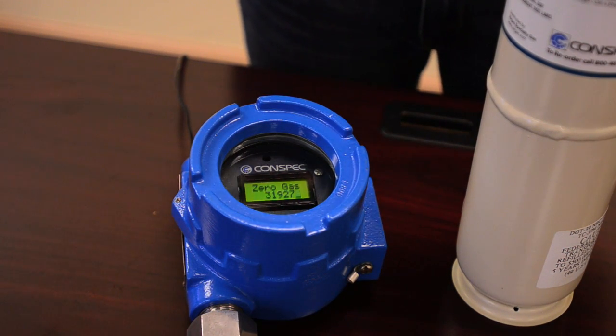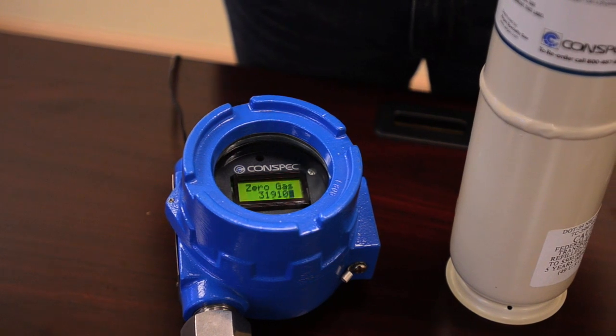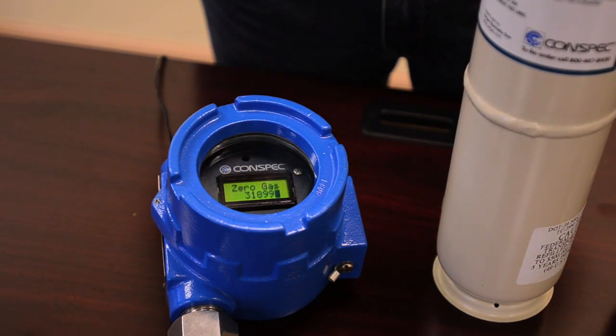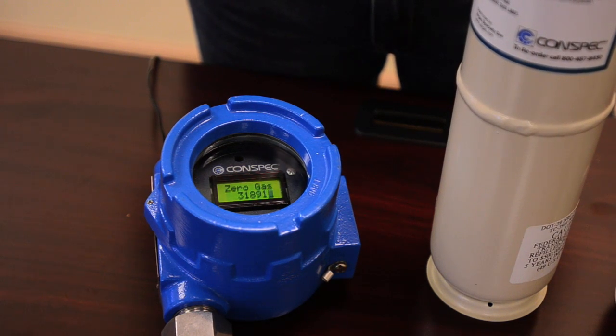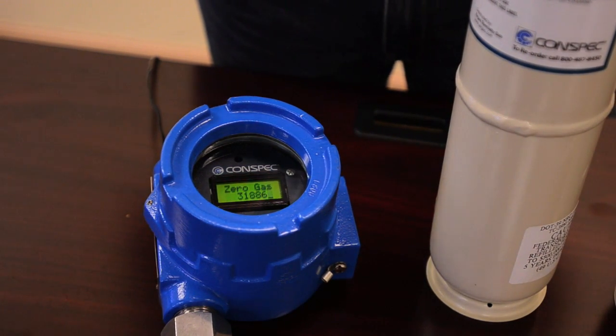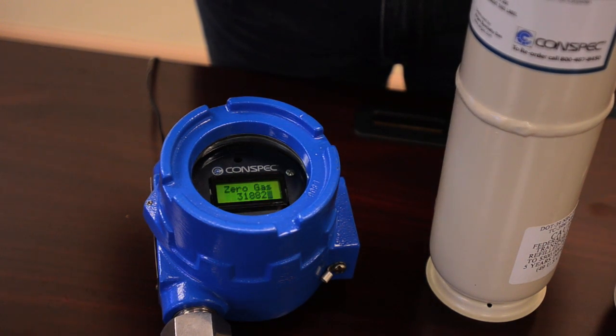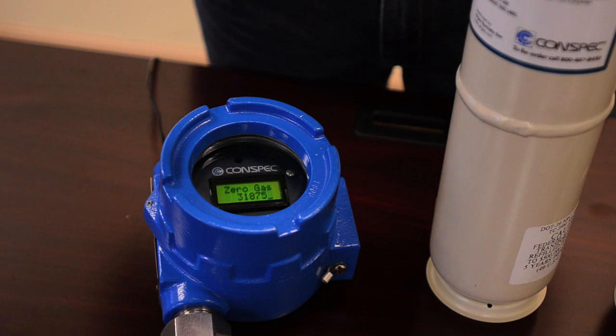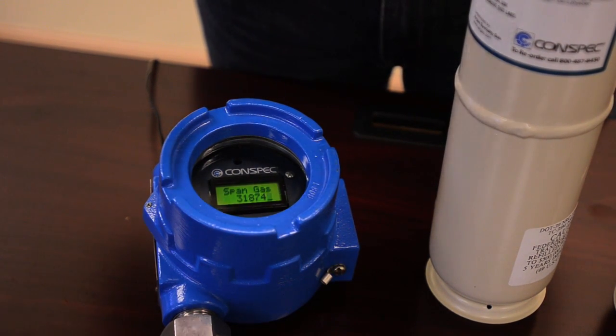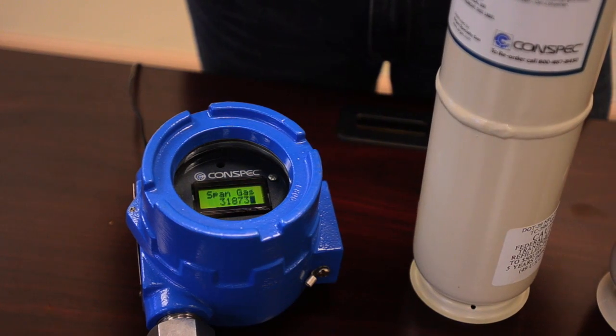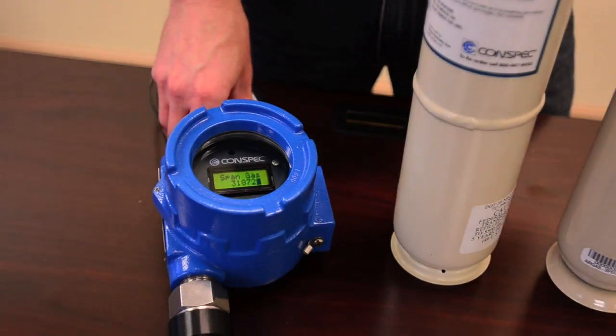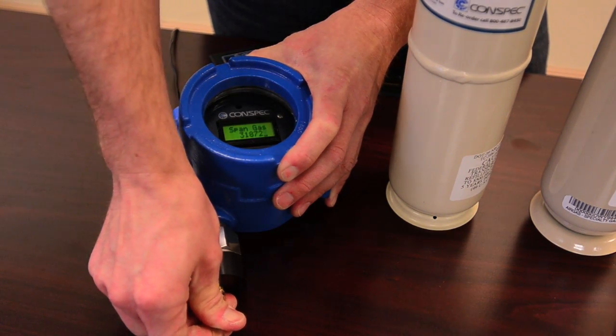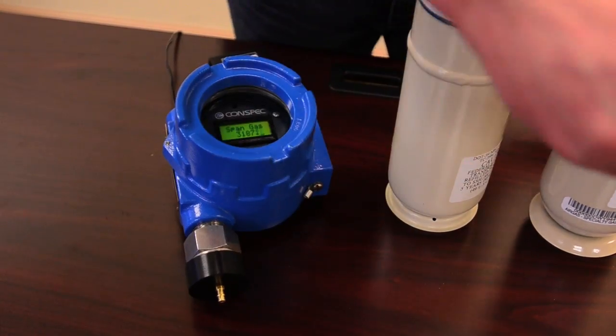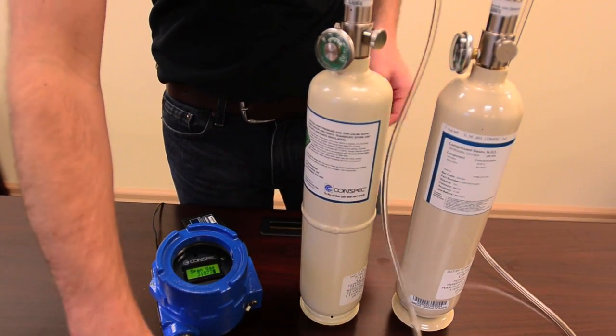The reason that we inject a gas that's similar to our atmosphere is we're letting the monitor experience a true zero condition that's free of the target gas, which would be methane here. And we're looking for more of a stable reading and a numeric value here. As long as your first 3 significant digits aren't fluctuating, it's a good indication that it's a stable reading. So we can go ahead and accept that value and then shut the calibration gas off. It's a good practice to accept the reading before you shut the calibration gas off in order to ensure a true reading. So at this point we can connect our span gas.